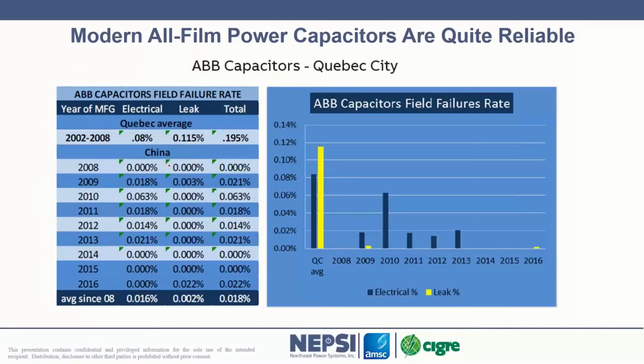This is from ABB Capacitor Group in Quebec City. I show this slide because it's interesting to note the failure rate for capacitors is very, very low, on the order of about 1 in 5,000. Capacitor technology has advanced in the past 15 to 20 years, when they have gone from polypropylene paper design towards polypropylene designs. The number of leaks and capacitor failures has gone down quite a bit.